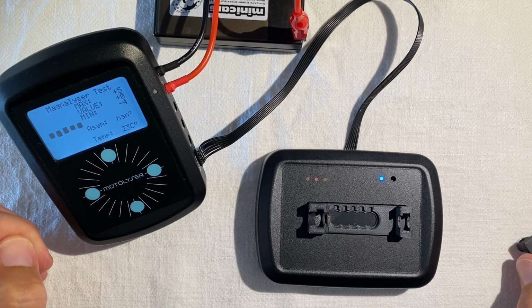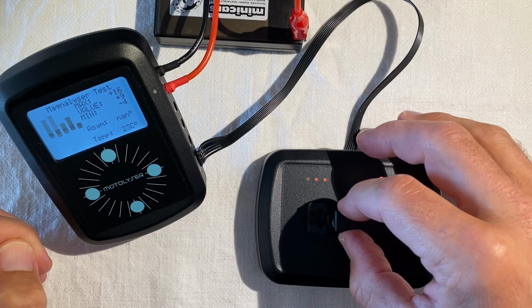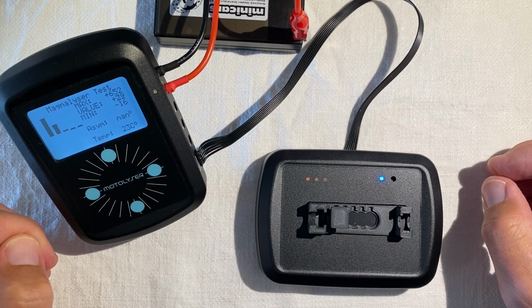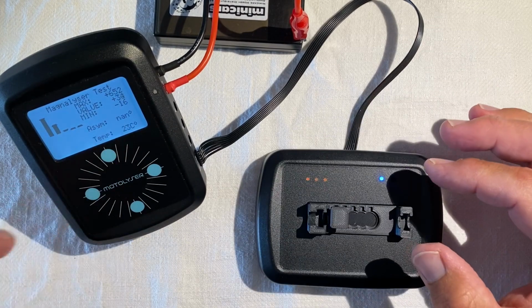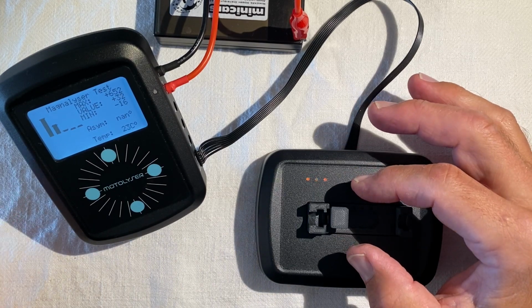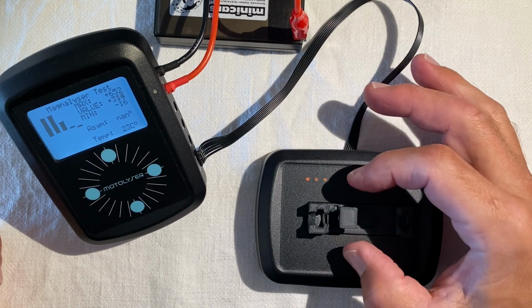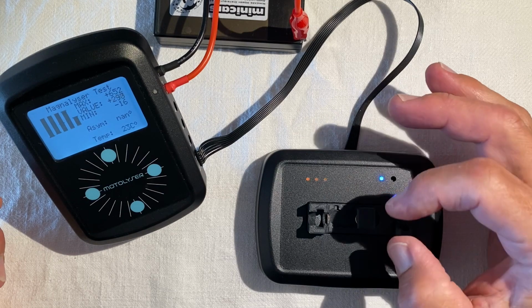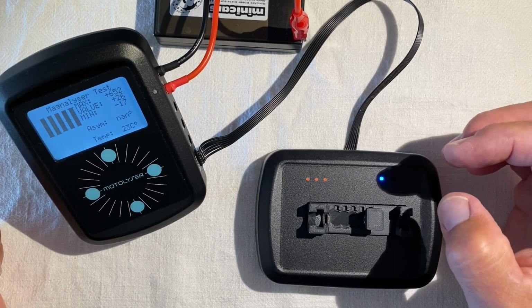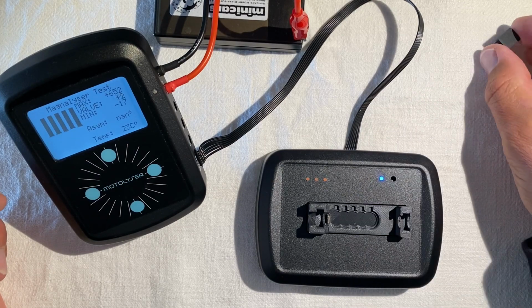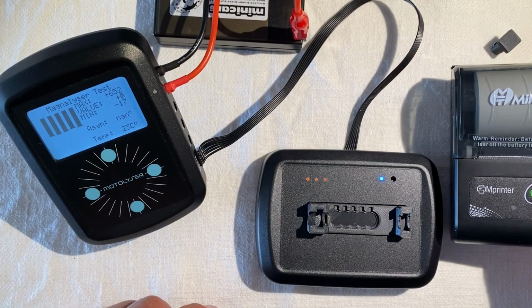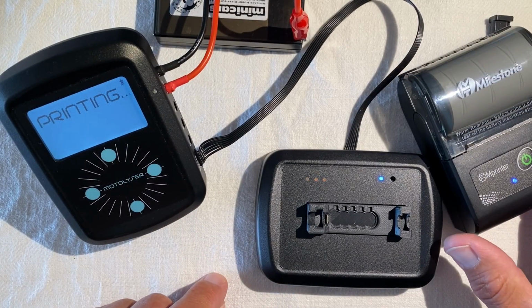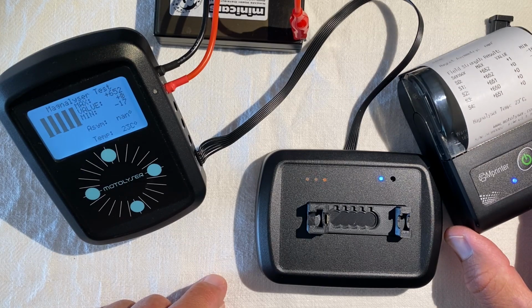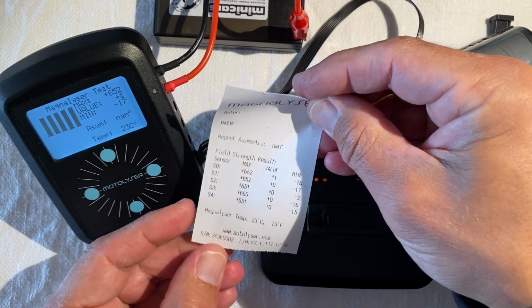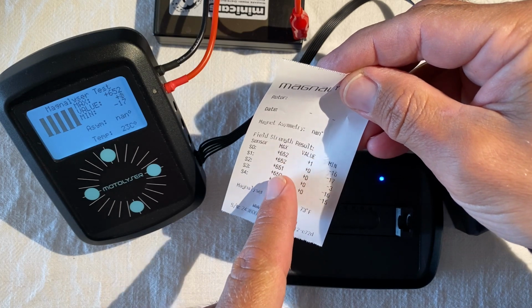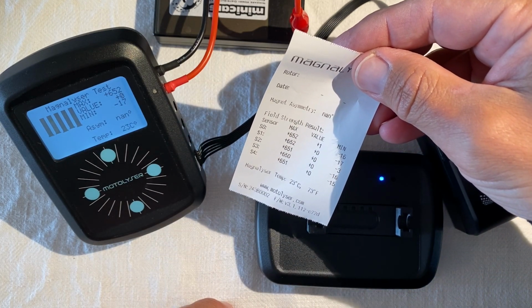When the calibration is done, you can always go back and validate it by placing the calibration magnet into the slot, and you should see a max value of whatever calibration reference value you had in your system. In our case, we had 650 when we started. So by doing this, placing the magnet in the different sensors, we can just recreate the values. And if you have a printer with your Magnalyser, you can bring that out, turn it on, and then hit the right button, and it would actually print out the results. Here you can see that all the max values are in line with the calibration reference, so the calibration is good.